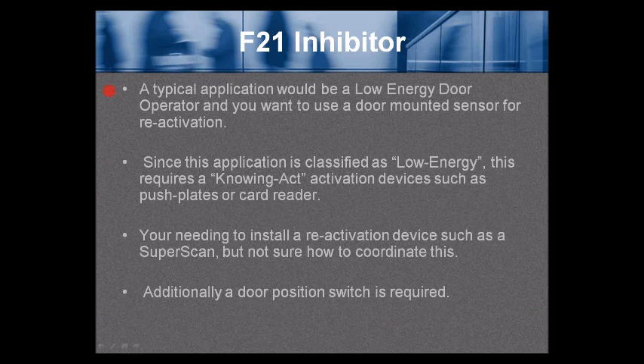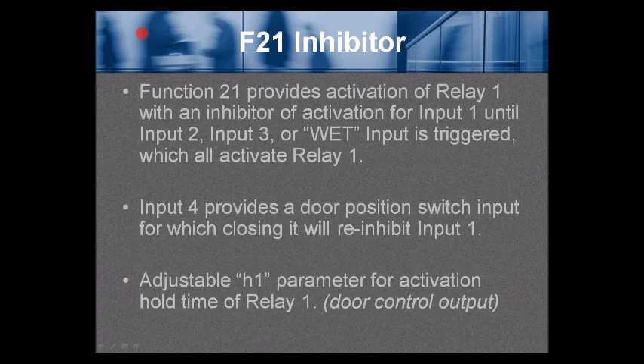Function 21 — inhibitor. A typical application would be a low-energy door operator where you want to use a door-mounted sensor for reactivation. Another example is a knowing-act door that uses a door-mounted sensor. Since this application is classified as low energy, it requires a knowing-act push plate as the activation device, such as a push plate or card reader. You may also need to install a reactivation device such as a SuperScan and need to coordinate it. Additionally, a door position switch is required.